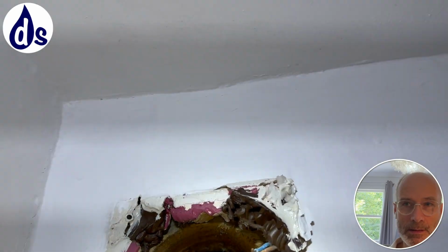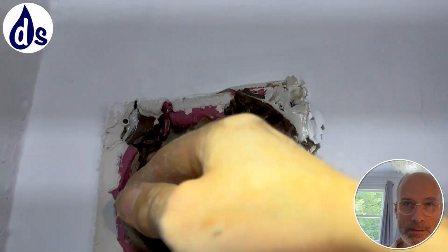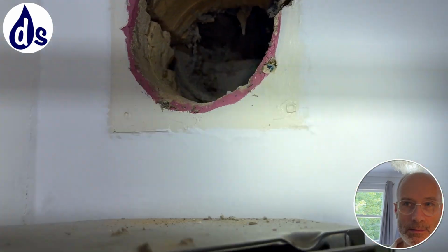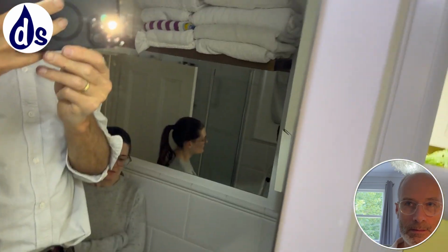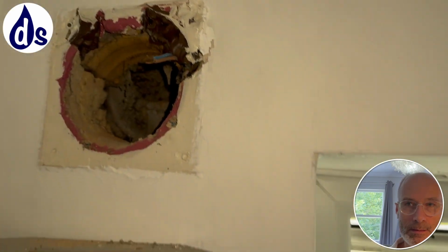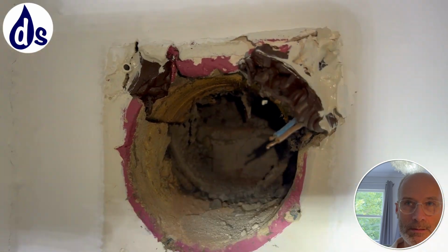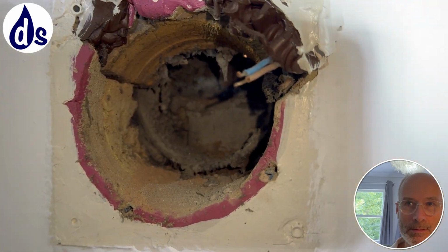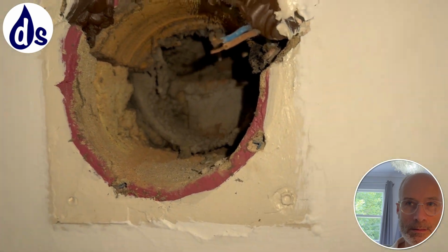So I'm going to recommend you get somebody to remove it from the outside. You could get a better fan, but it's probably not the fan's fault. It's just blowing. You can see it, can't you? Yeah, it's just sealed up, so it's just blowing the air back in, basically, whereas very little is coming out.